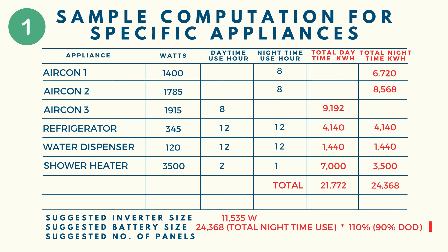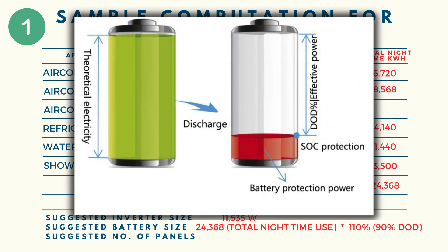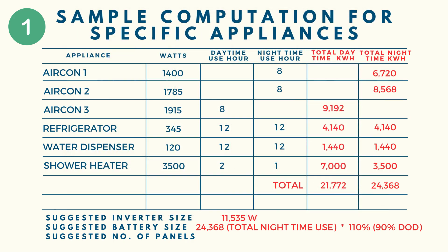For the battery size, if the purpose is nighttime use, look at the total nighttime kilowatt-hours — that is your battery size. However, we need to consider 90% DOD (depth of discharge), meaning only 90% of the battery will be used. The remaining 10% is the SOC (state of charge). This improves overall system efficiency, and fully draining the battery can shorten its lifespan, so we should never fully drain it.